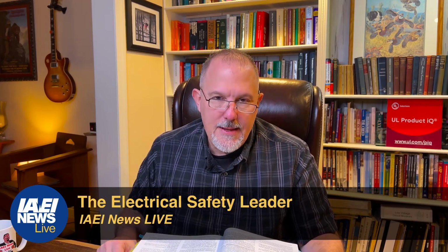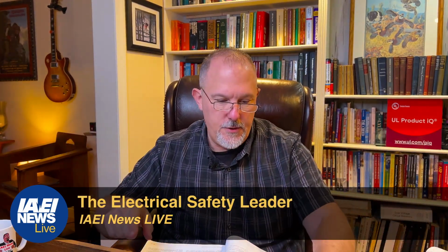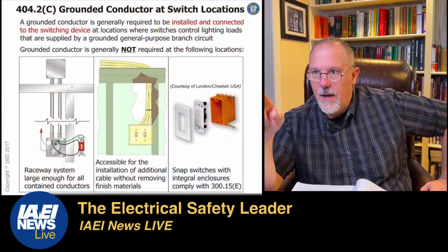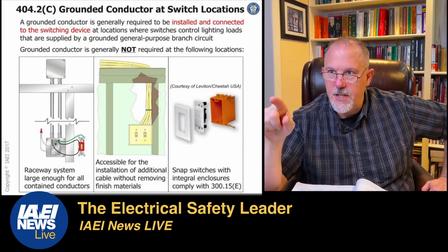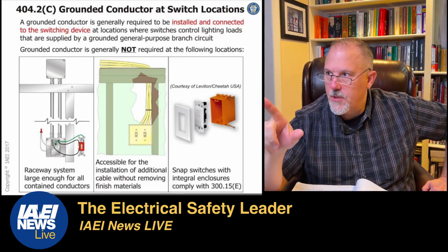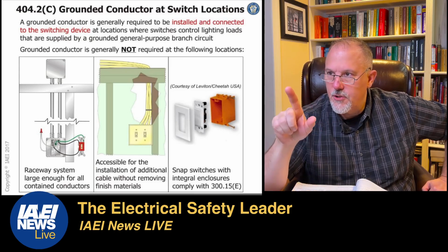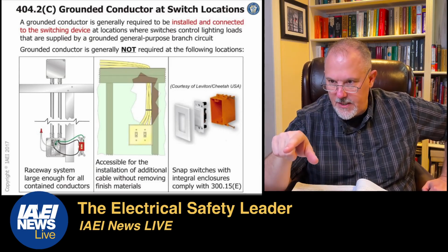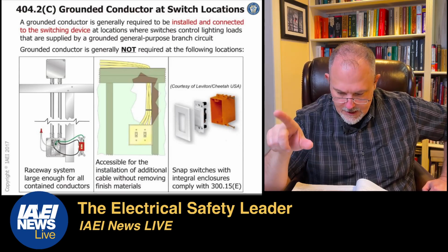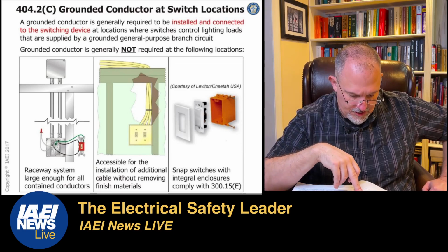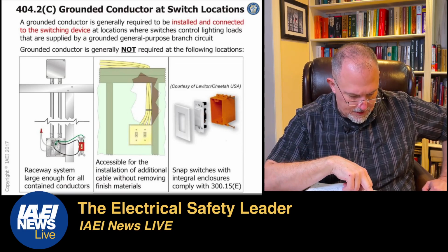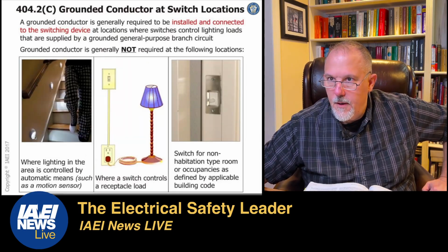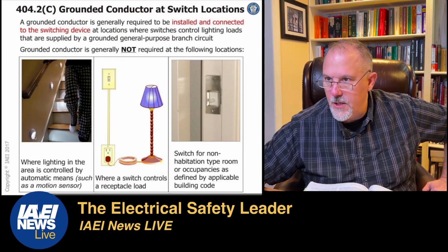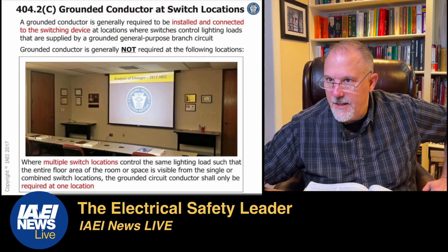Okay, so they made that change in the '14 code. And then in the '17 code, they said that a grounded conductor is generally required to be installed and connected to the switching device. So we already know that. At locations where switches control lighting loads that are supplied by a grounded general purpose branch circuit, the grounded conductor is generally not required at the following locations. Raceway systems, we know that. We know this. 404.2(C). Oh, I see what they did. Okay, so a grounded conductor is generally required. So here's what they did.